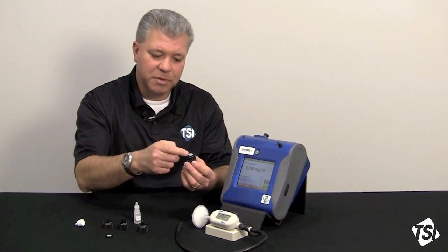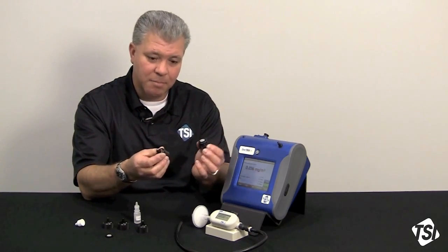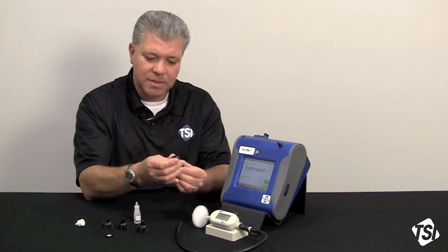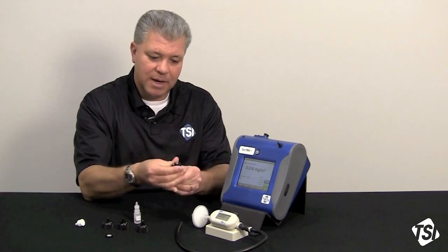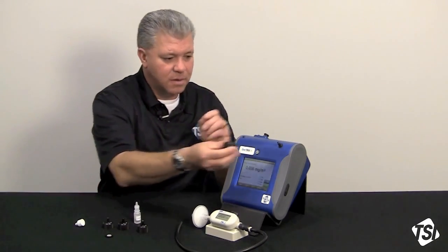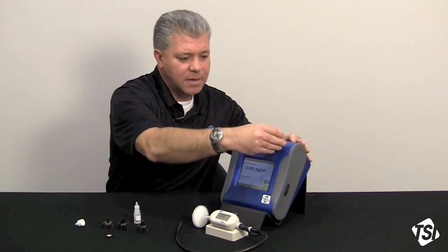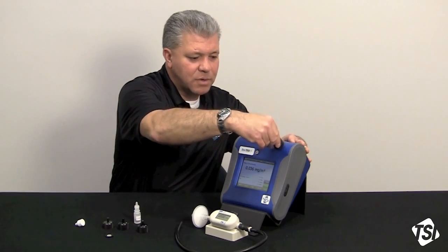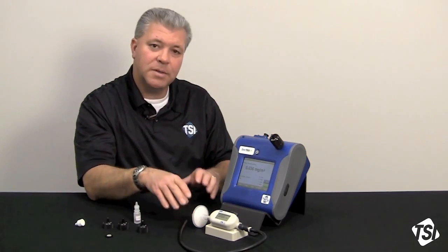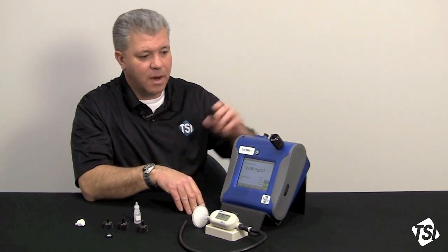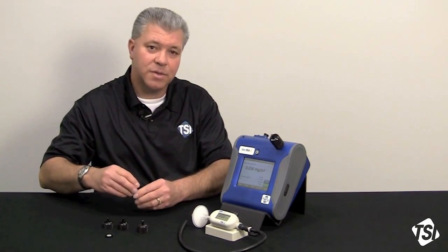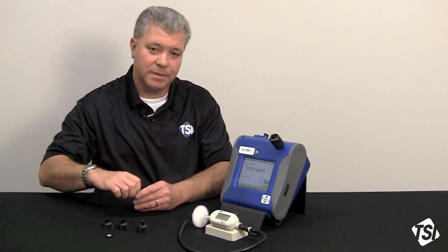So what we do is we put the little impactor head inside the bottom portion of the impactor. We screw on the top, and in this case it's a PM10 inlet head. Once we screw that on snug, we put that onto the inlet of the DustTrak 2, twist it as you put it on, and now we're ready to do a flow calibration. The flow calibration for all of these impactors is 3 liters per minute.